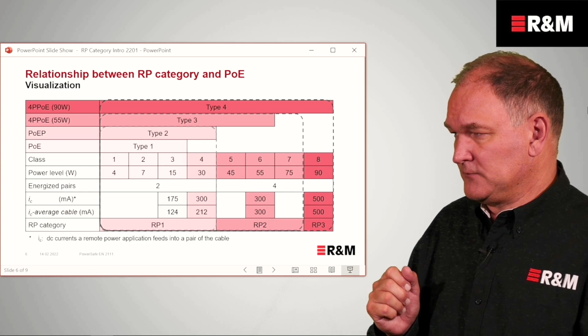Now, obviously, in a bundle, you could have different applications, and there are different ways how you can do that. And the standard allows and gives you ways how to calculate for it. One way is with tables where you have the relationship between, for example, here, a PoE plus and a type 4 four-pair PoE. On the horizontal axis, you would have the percentage of cables in the bundle with PoE plus, for example here with 2/3, 66% of the cables being used for PoE plus.